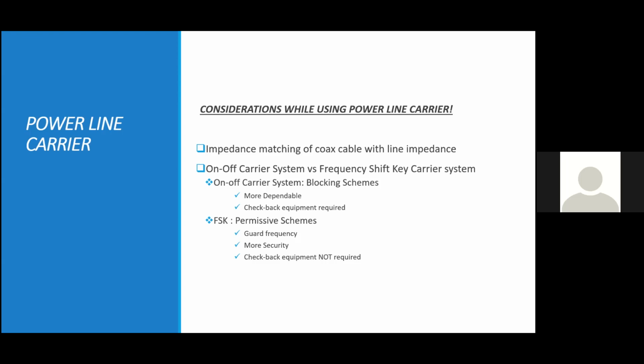And the second thing we should be considering is what kind of carrier system we are using. Is it an on-off carrier or a frequency shift carrier? So on-off carrier is basically a carrier which stays off in normal condition and turns on when there is a fault, or if the local relay needs to communicate something with the remote relay, the carrier system turns on. Whereas the frequency shift carrier system always stays on at a particular frequency, and that frequency is called the guard frequency. So this kind of carrier system improves the security, and both the relays are able to tell if the carrier channels are healthy or not.